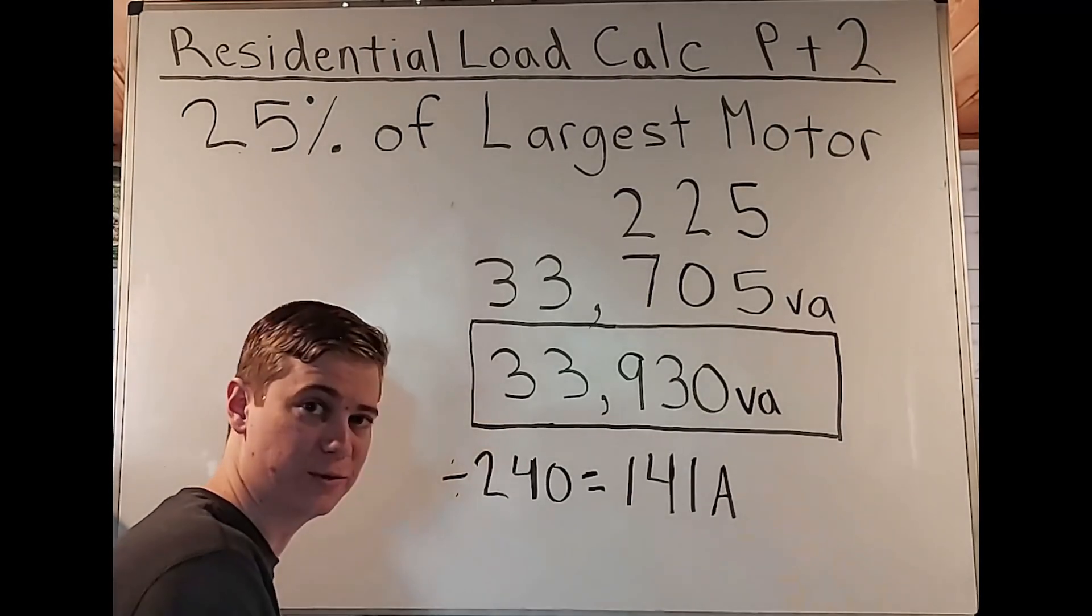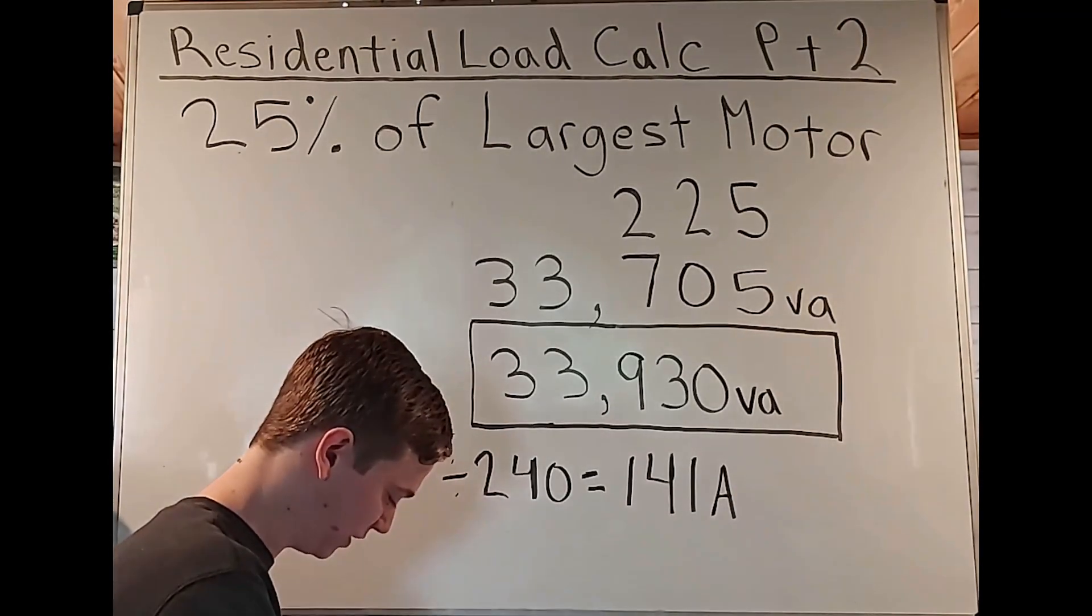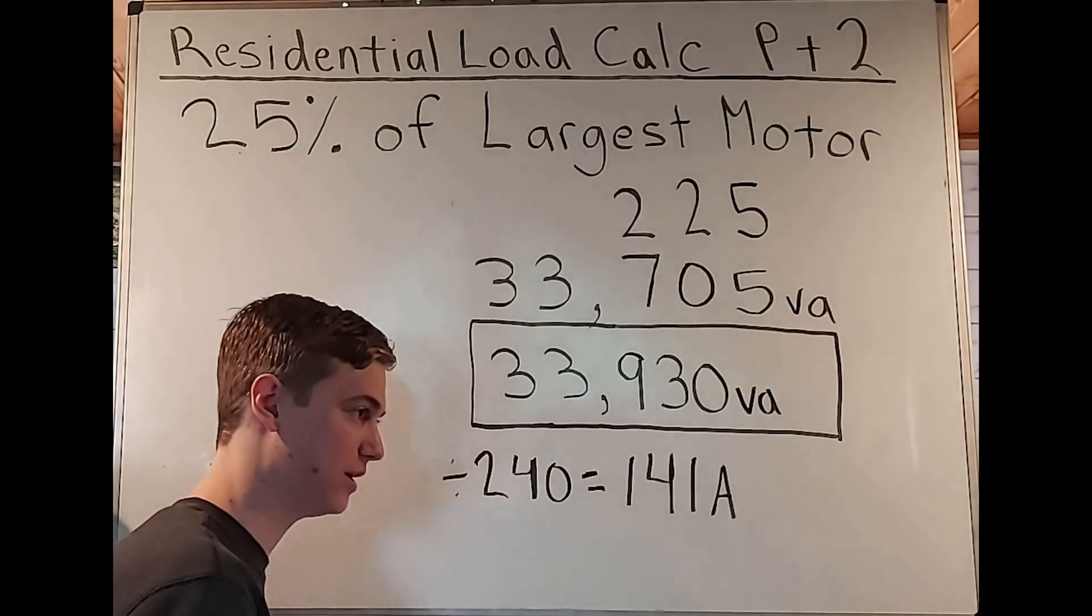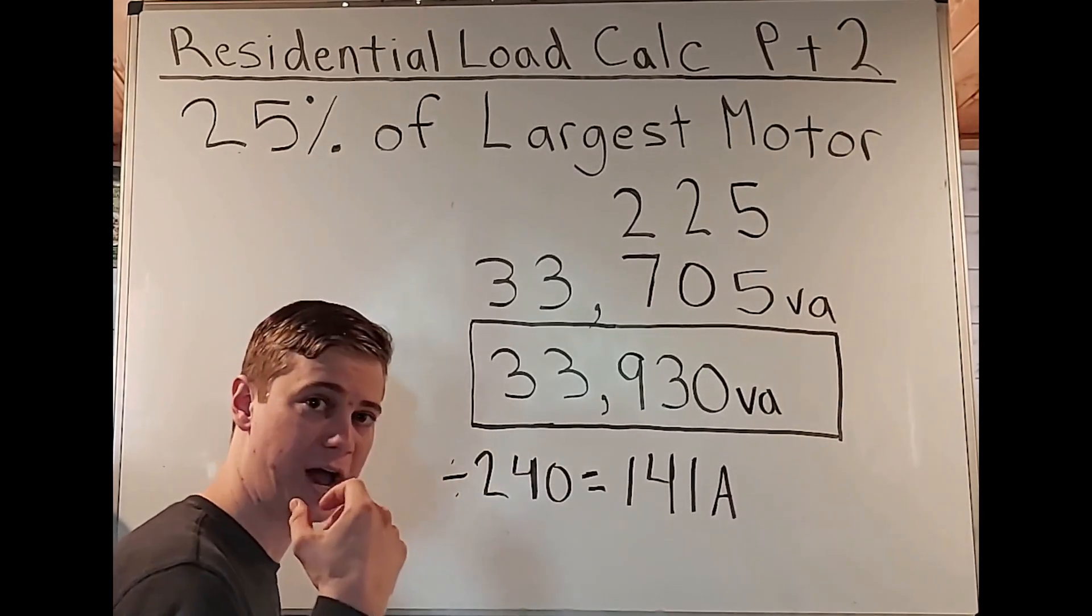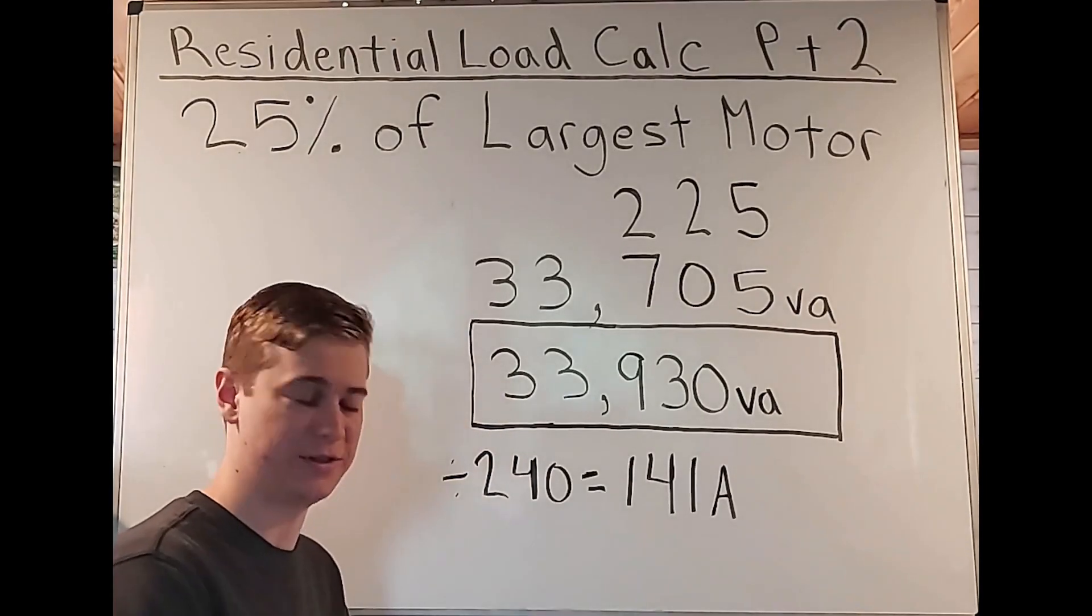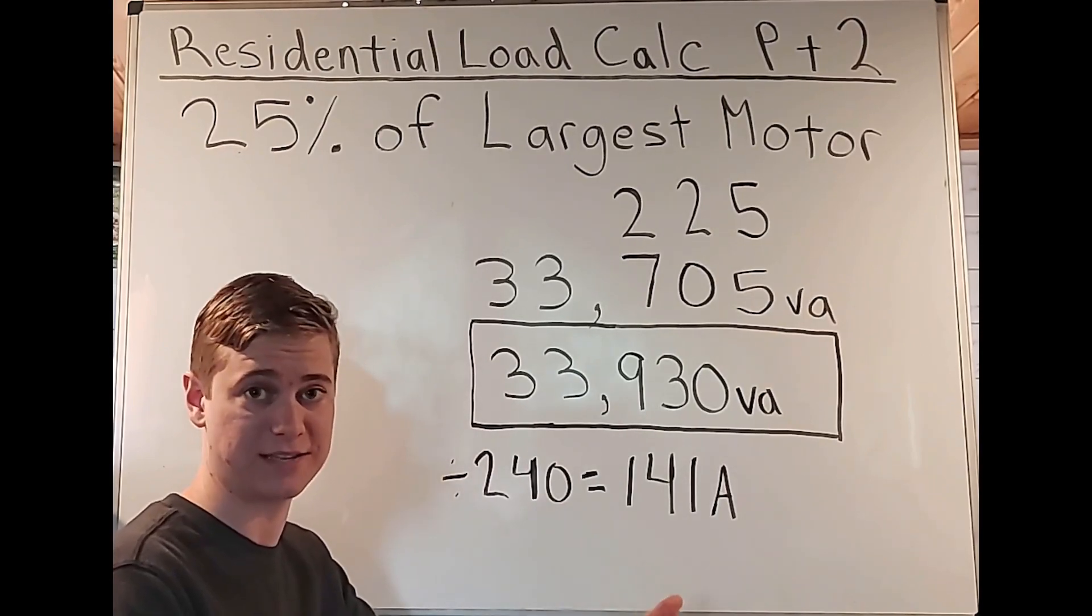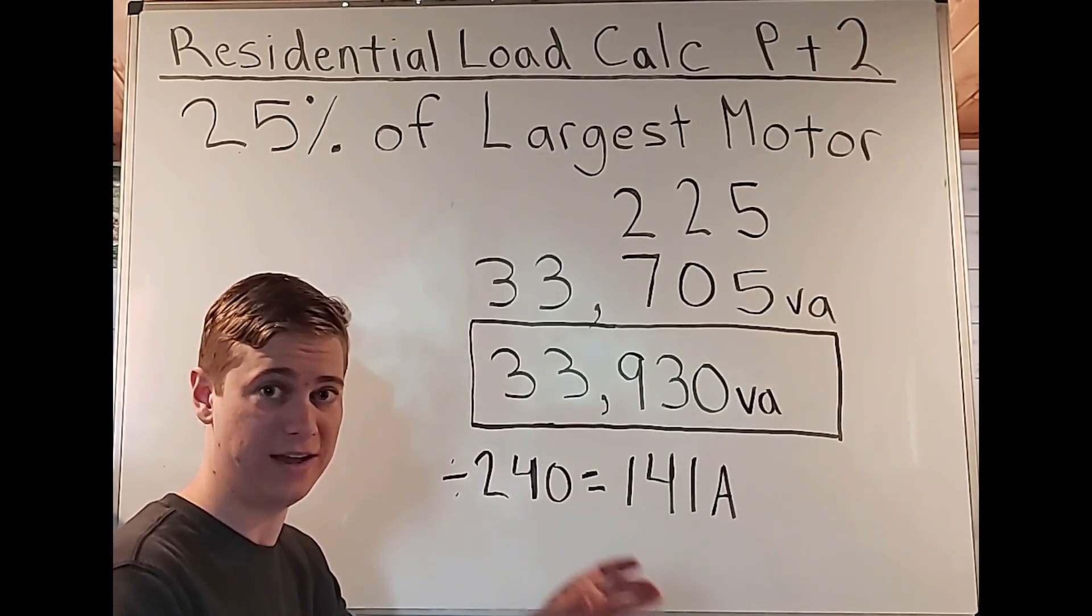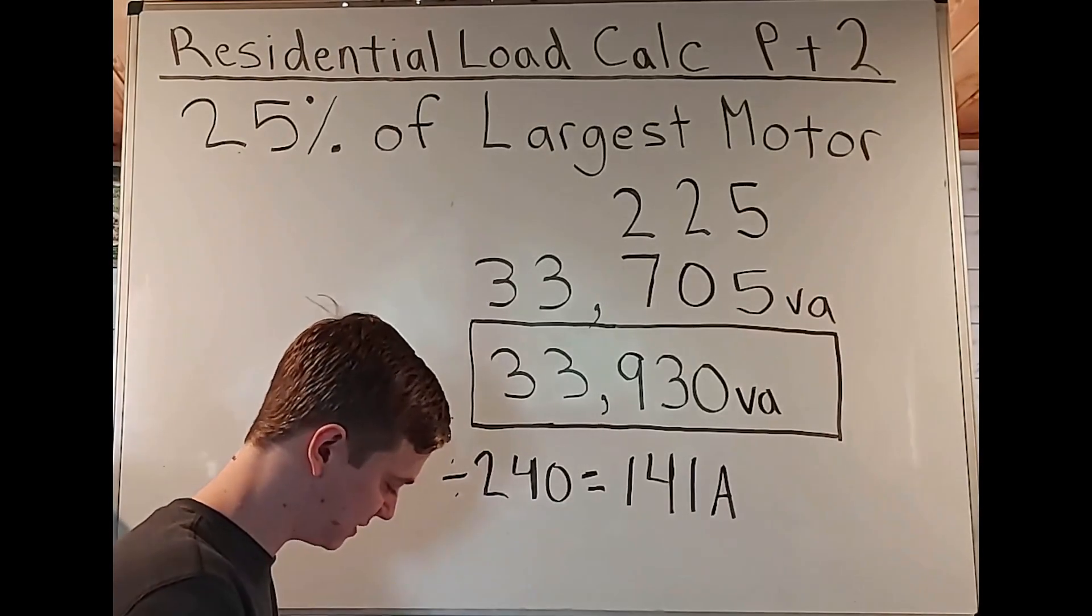And that is that the ampacity of the conductors does not correspond with what they call a standard amperage rating. This is of course of a fuse or a circuit breaker. So that's where, when we're looking at table 240.6A, we saw the 125 and we saw the 150, but we're dealing with 141.